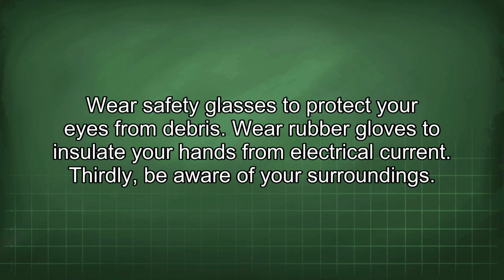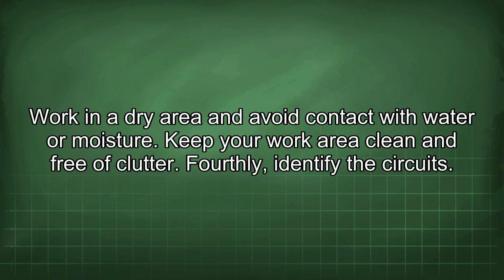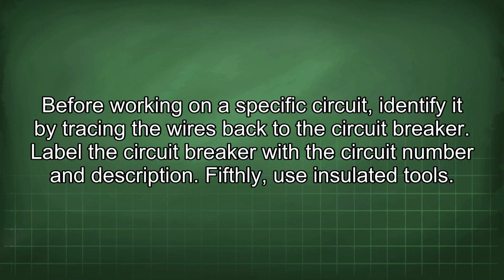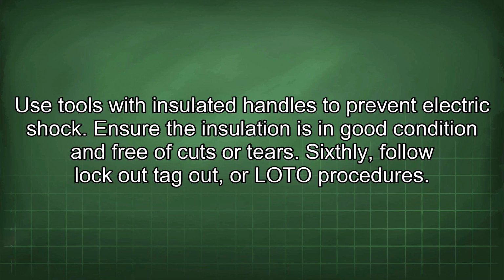Thirdly, be aware of your surroundings. Work in a dry area and avoid contact with water or moisture. Keep your work area clean and free of clutter. Fourthly, identify the circuits. Before working on a specific circuit, identify it by tracing the wires back to the circuit breaker. Label the circuit breaker with the circuit number and description. Fifthly, use insulated tools. Use tools with insulated handles to prevent electric shock. Ensure the insulation is in good condition and free of cuts or tears.